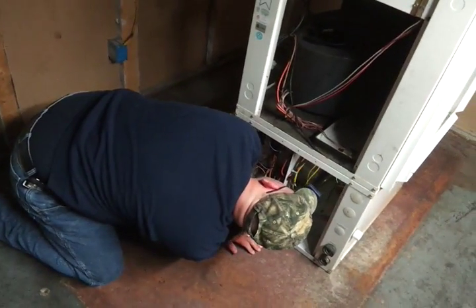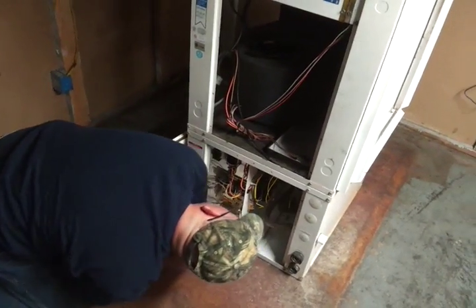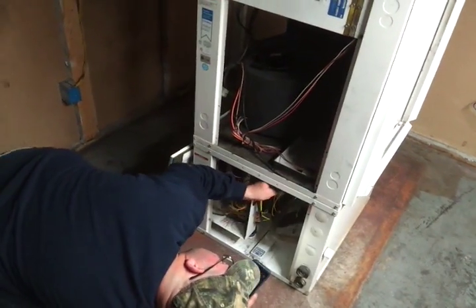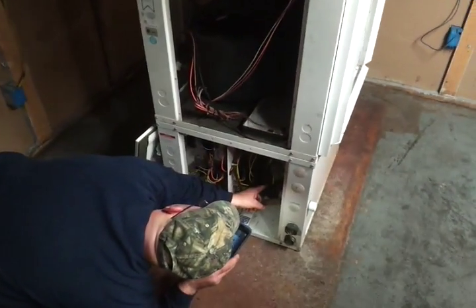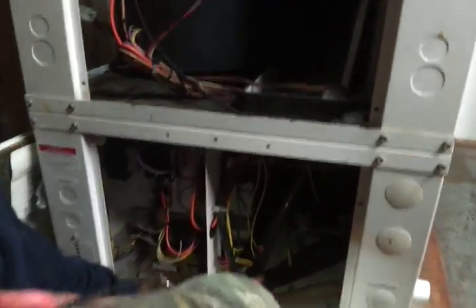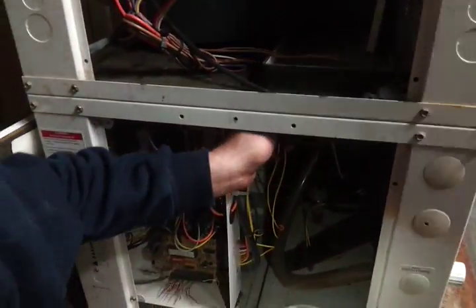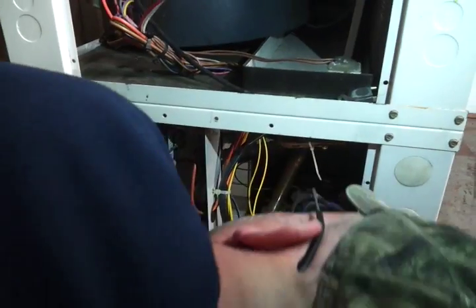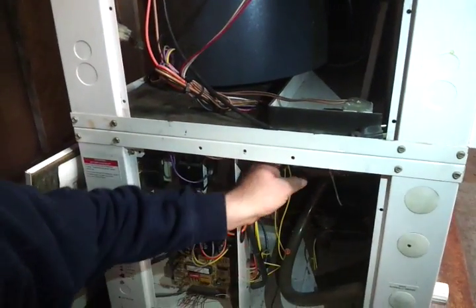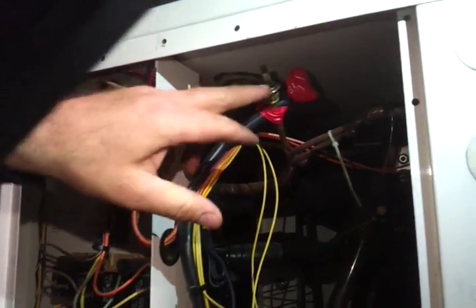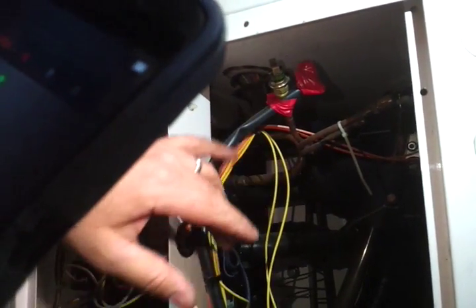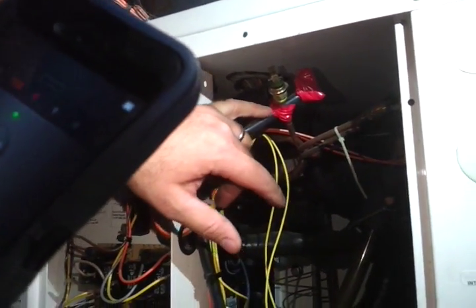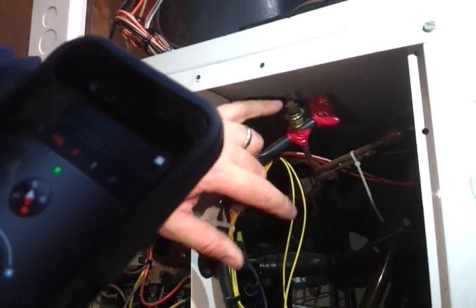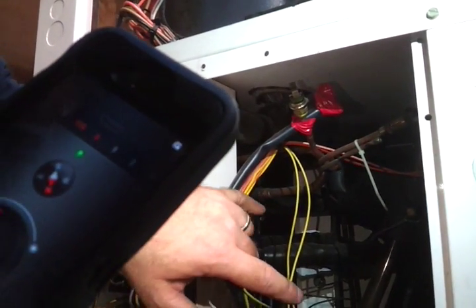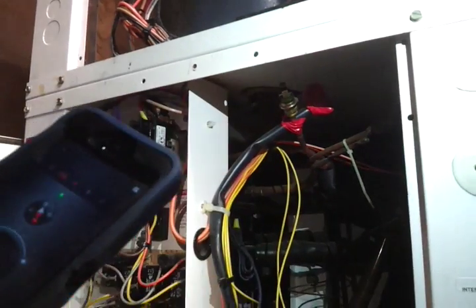Oh yeah, nice old thermostat, it's a WaterFurnace thermostat, with a little sun damage. The temperature sensor is disconnected, and they've got a high pressure switch disconnected too, just wire-nutted together. This is a high pressure switch, so when the refrigeration pressure on the high side gets too high, it will break the circuit, shut the compressor off, and throw it into a lockout.